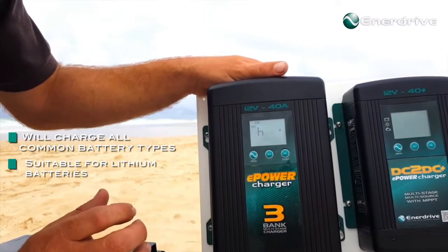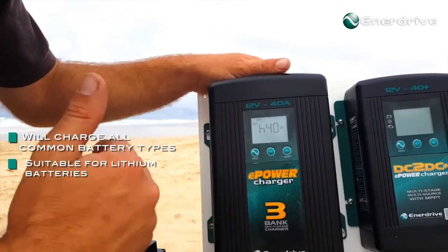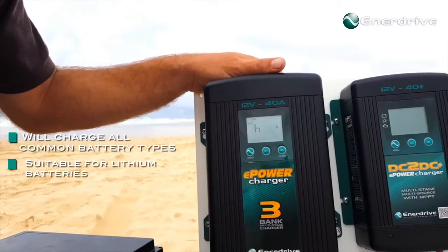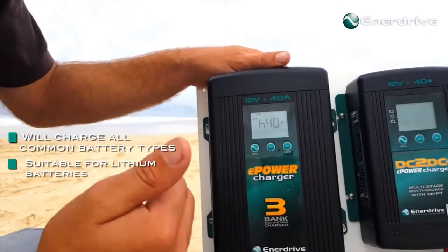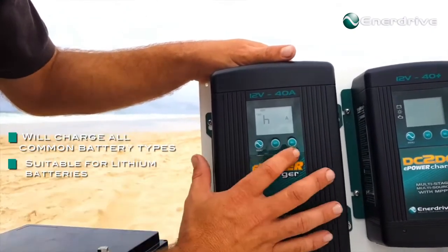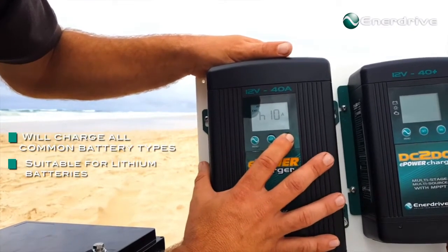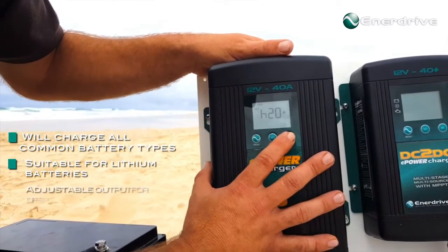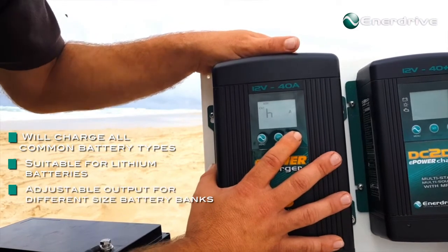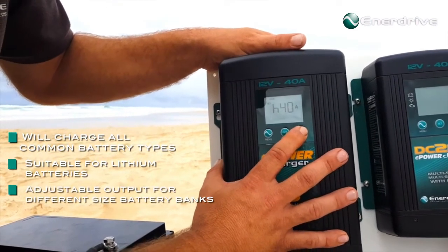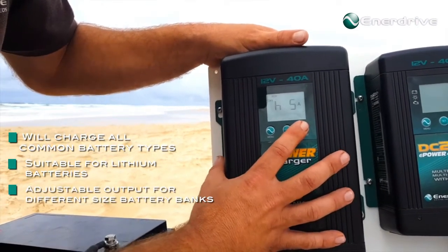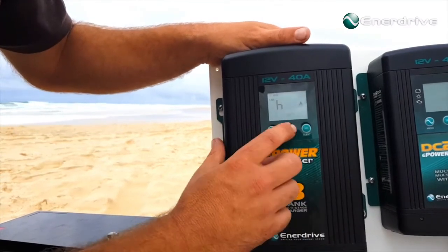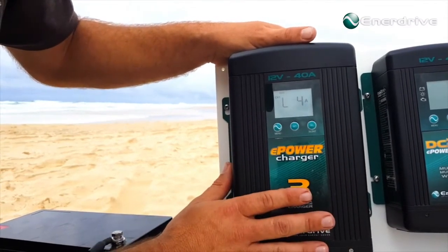Now I don't want my output to be 40 amps. I bought a 40 amp charger in this case to future-proof my system in case I add to my battery bank, but I've only got, let's say, a 100 amp battery. So if we just hit the select button, we can bring that down to make it a 10 amp output charger, 20 amp output - it doesn't matter, whatever you require. In this case we can leave it at 40 amps, or go back down - let's go 20 amps, so we hit set there.